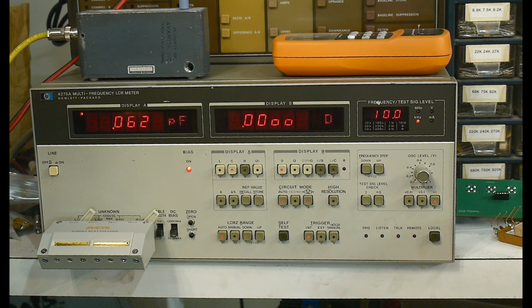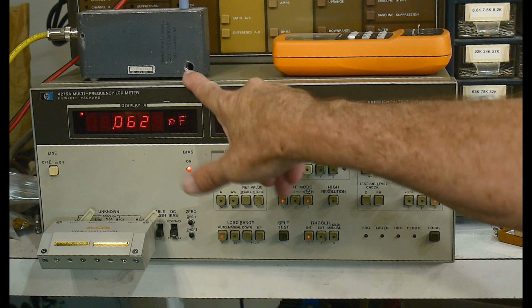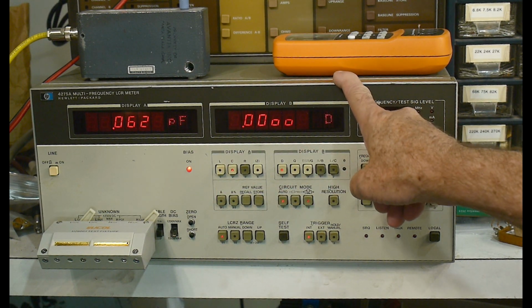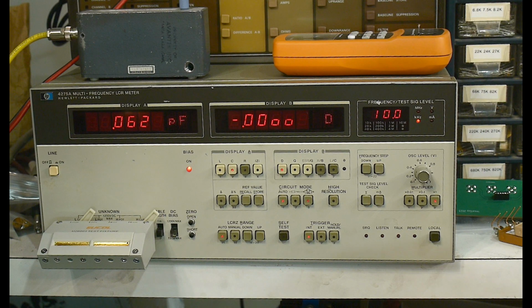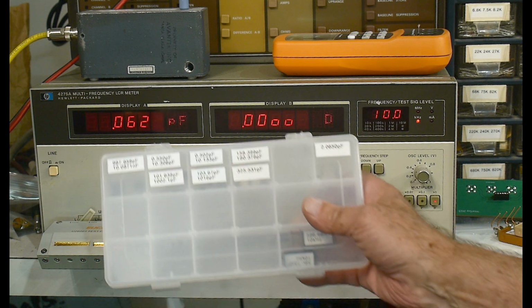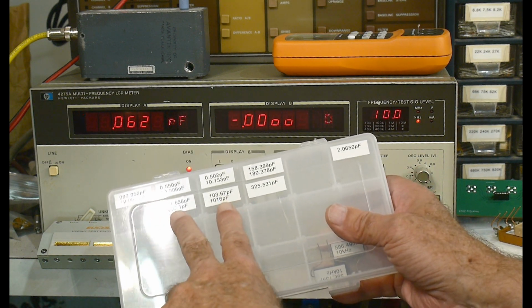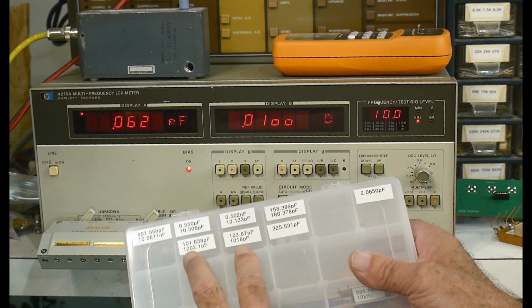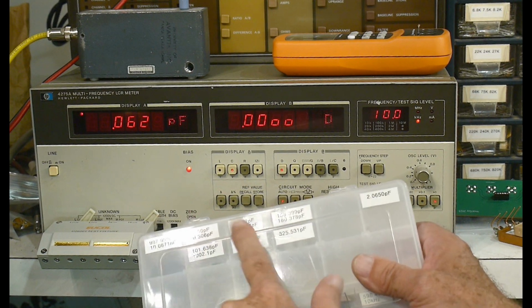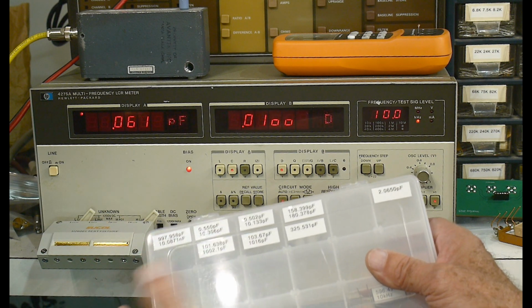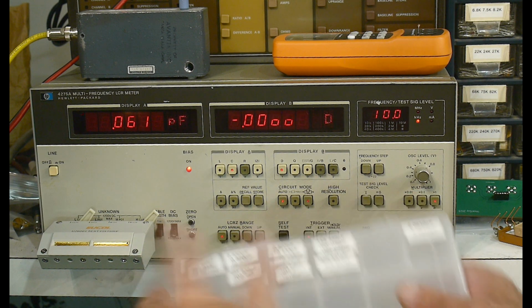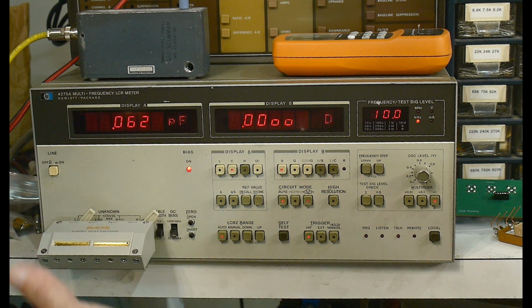All right. And you needed a 1, 10, 100, 1000 picofarad standards. And Hewlett-Packard will sell you those. I think they're about $10,000 to buy those 4 capacitors from Keysight these days. But I've made some secondary standards here. So I made 2 sets of secondary standards for 1, 10, 100, and 1000. So I have these as a secondary and these as a secondary. They're not the exact numbers, like it's 10.306. So when I calibrate, I adjust it to 10.306 instead of 10. So it's no problem at all using secondary standards.